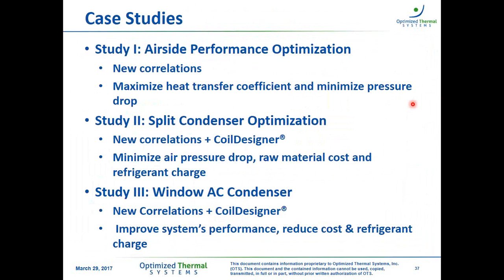The second one is an actual application for a split condenser optimization, where we use new correlations and CoilDesigner to optimize this heat exchanger, targeting minimizing the air side pressure drop, the raw material cost, and the refrigerant charge. And the last one is a study also on a window AC condenser, where we were focusing on improving the system's performance, reducing cost and refrigerant charge.